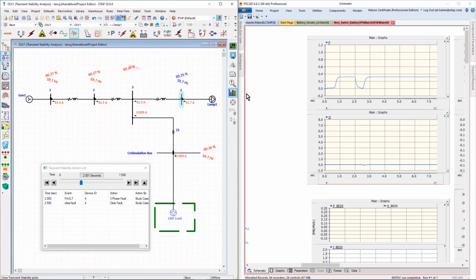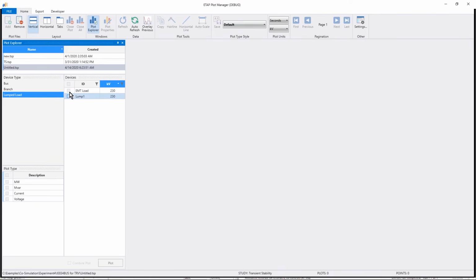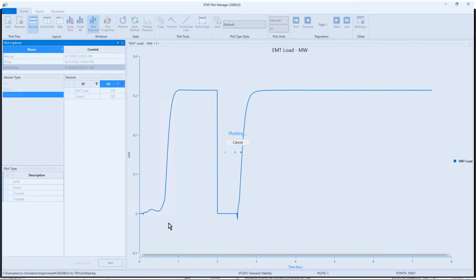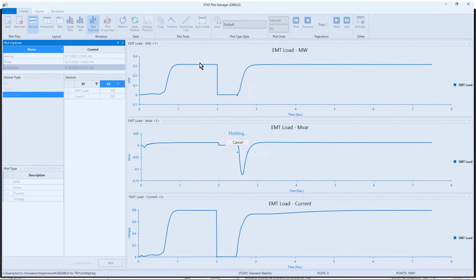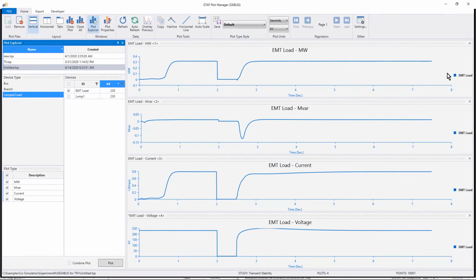You can also visualize the results, and in this case we can go ahead and plot our EMT load and observe megawatt, megavar, current and voltage as a combination. And this essentially shows us the exact same response as we saw on the PSCAD side, which is the RMS response from ETAP, while we were observing the PSCAD EMT calculations within PSCAD environment itself.